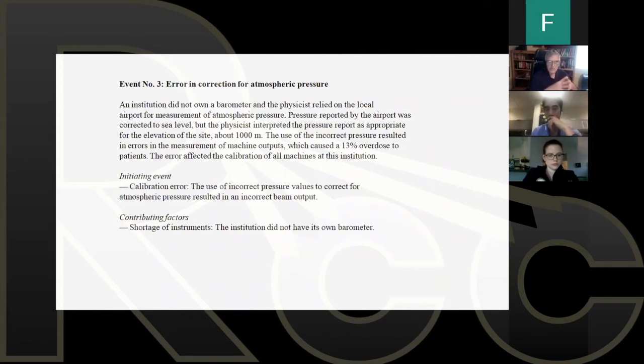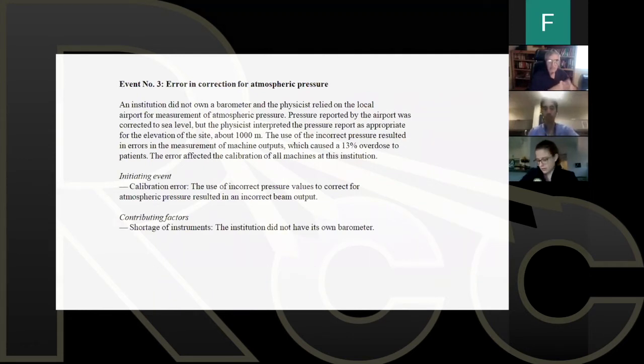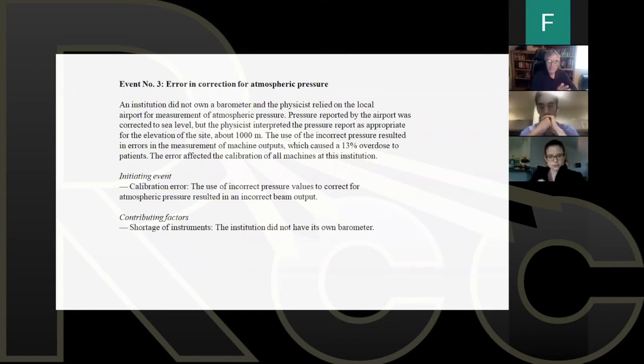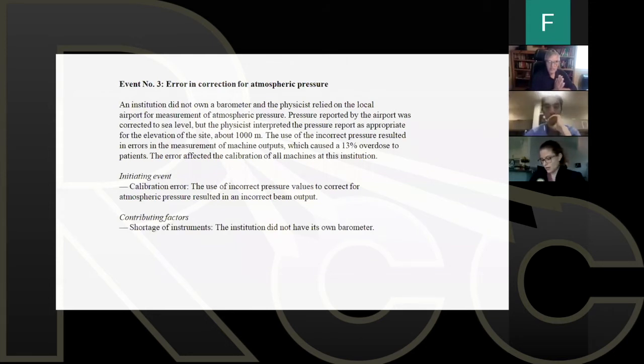In this particular situation at 1,000 meters, it resulted in a 13% overdose to patients. And the error affected the calibration of all machines, all patients, every treatment. The use of incorrect pressure to correct for atmospheric pressure resulted in an improper calibration, a very, very serious 13% error.